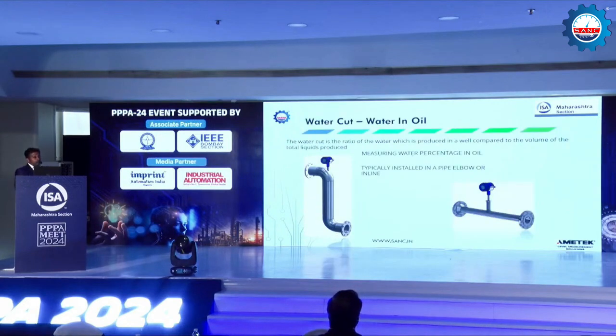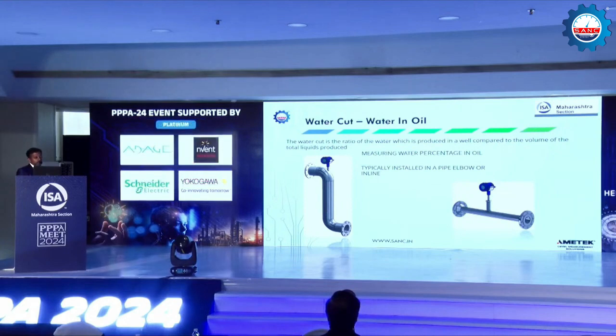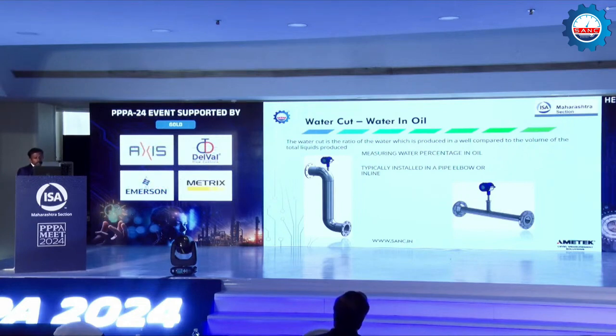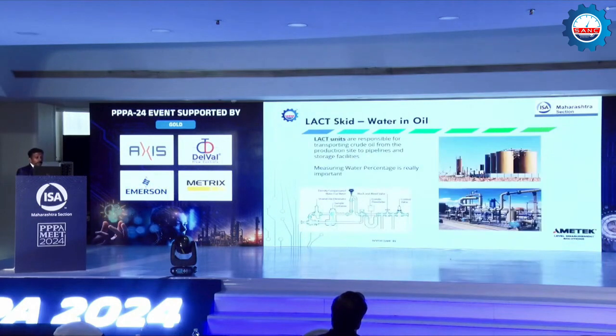The other application I'm going to talk about today is the water cut, or we can say water in oil. The installation will be like this, on the vertical pipe and also in the spool piece. This is not level measurement, it is quite different. What we are doing here is measuring the water percentage in an oil. That is what we measure with this RF admittance technology.